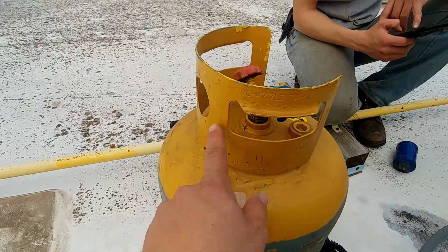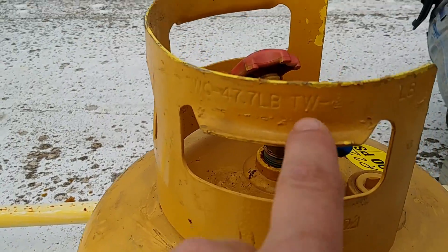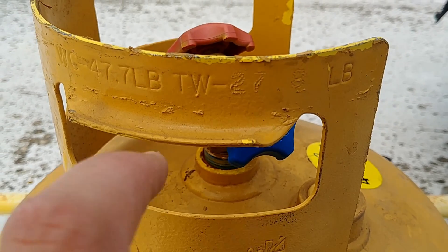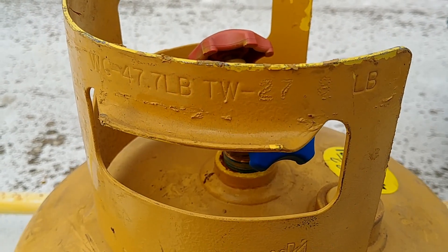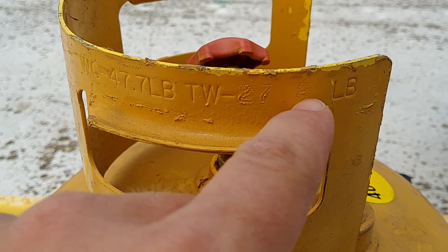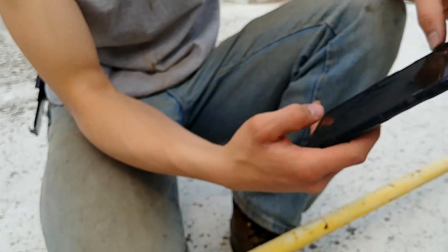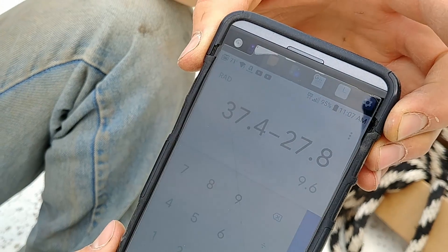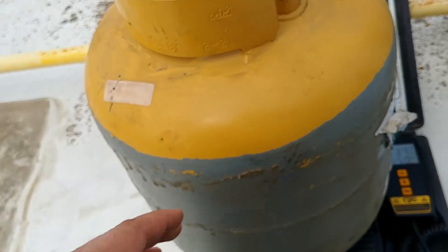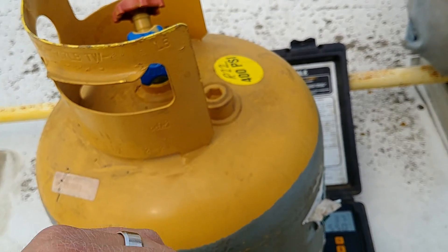And if you look on the side of the tank somewhere, you'll find somewhere where it's stamped TW. You see right there it says TW? That stands for tare weight. The tare weight of this particular tank is 27.8. So 37.4 minus 27.8 is 9.6. So this system had about 9.6 pounds of refrigerant in it.